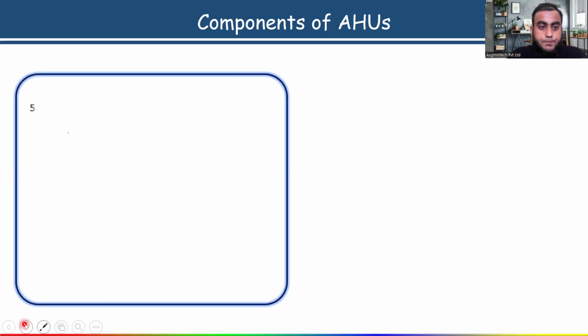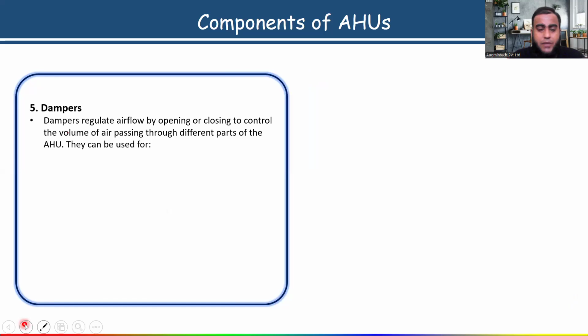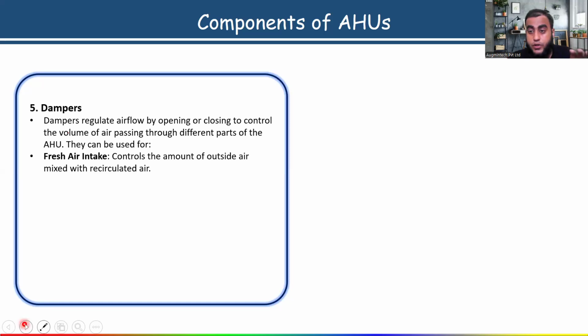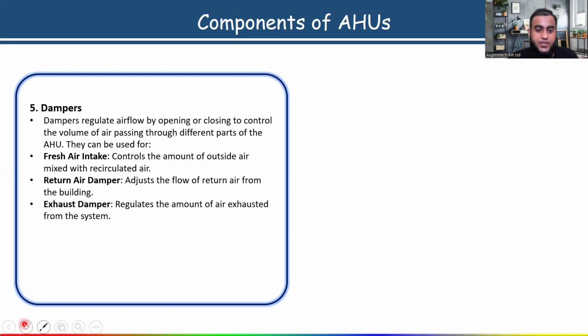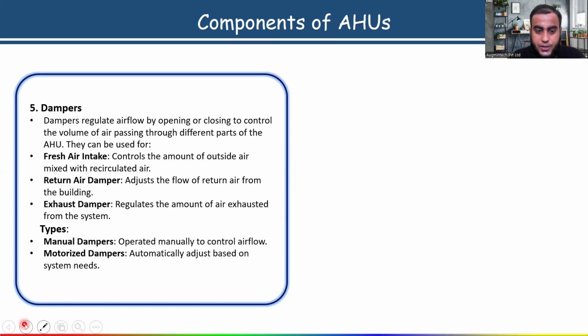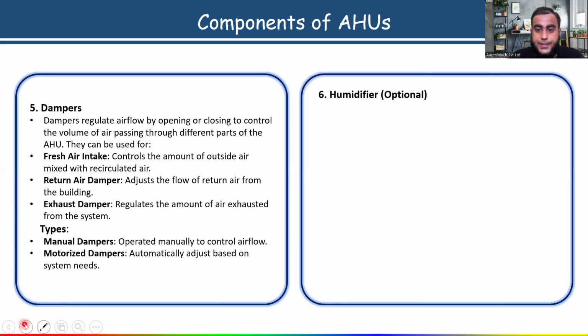Next are the dampers. The main purpose of dampers is to regulate airflow by opening or closing to control the volume of air passing through different parts of the AHU. They can be used for fresh air intake, which controls the amount of outside air mixed with recirculated air. In the same way, in the return air we also have to install a return air damper, which adjusts the flow of return air from the building. Then the exhaust damper regulates the amount of air exhausted from the system. Manual and motorized dampers are also there. Is this clear?